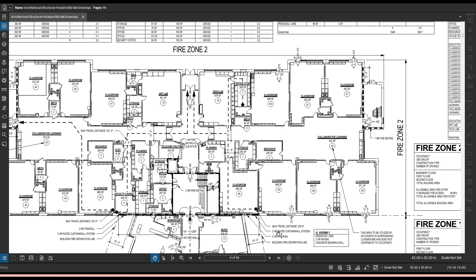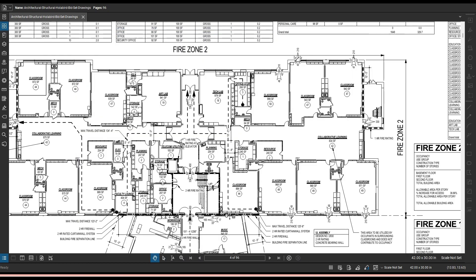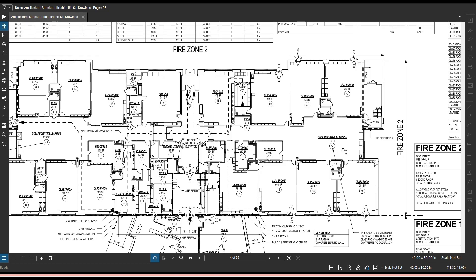So that's what that means. Now, here you see a two hour rated curtain wall system, and we see that this is the same pattern that we saw below. So what this is basically saying is that the curtain wall system, meaning a window wall system, has to have certain fire rated properties applied to it. So the sealant that's used around it needs to also be fire rated. It needs to hold up for two hours in the case of a fire. And so you can kind of follow and see which areas are getting those ratings. You'll notice it in stairs.